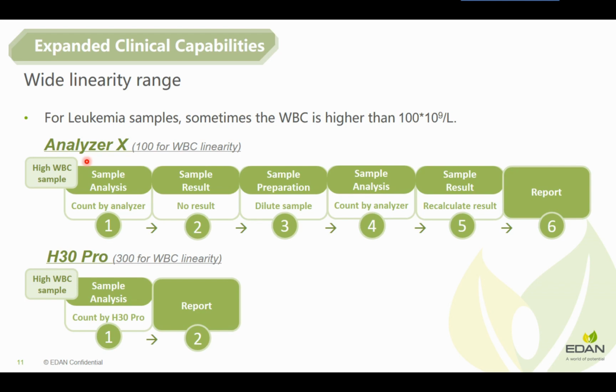If they encounter high white blood cell samples, it will be a complex process to get the results. Imagine that you will need to test the sample first, and then you find you can get no result on it. Then you will have to manually dilute the sample with the proper dilution ratio, and then test the sample again. After that, you will still need to calculate the results based on your dilution ratio. Finally, you got your results.